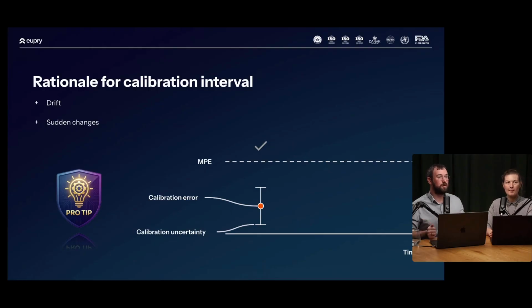The second thing is what we call sudden changes. I think that's a very nice way of saying, what do you call it, when something slips your hand and you drop something. Those are the most normal occurrences. Temperature sensors today are very, very stable, but if you do give it a large mechanical shock, it's going to drift rapidly at one point in time. More seriously, it is for relative humidity sensors. Relative humidity sensors are often, most types are really prone to chemical compounds, for example, and they're going to show a very large amount of drift. But the whole point here is that we are trying to predict the future. And of course, that's going to be impossible.